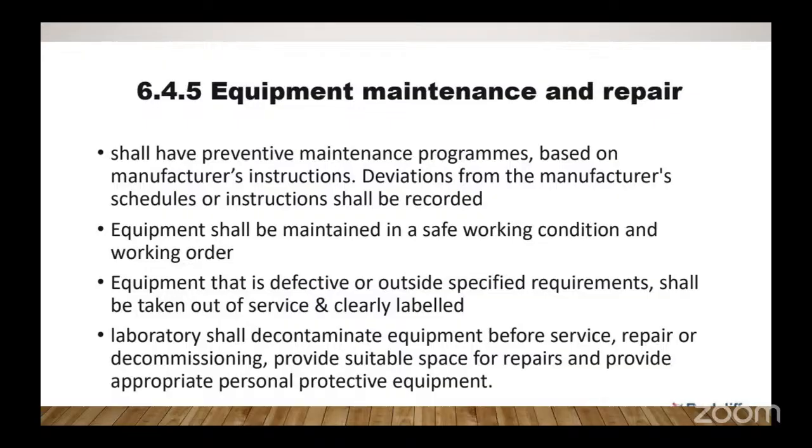Somebody read 6.4.5. Equipment maintenance and repair shall have preventive maintenance programs based on the manufacturer's instructions. Deviation from the manufacturer's schedule or instruction shall be recorded. Equipment shall be maintained in a safe working condition and working order.